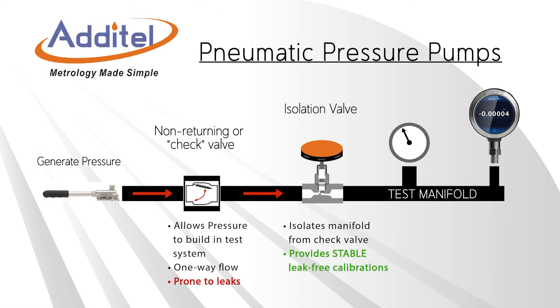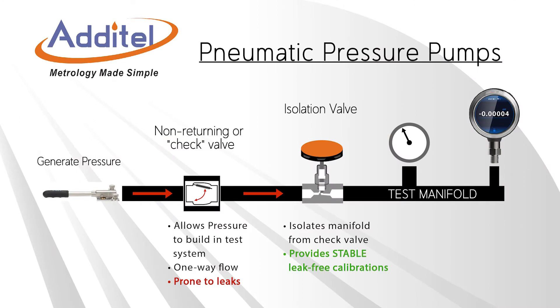A major design advantage of all Additel pneumatic pumps is an isolation valve that allows leak-free stable calibrations. Most pneumatic pumps in the market have non-returning or check valves that allow for pressure to be built up in the test volume. These types of valves are a source of leakage over time. Additel pumps include a valve that isolates the calibration volume from the check valve, providing stable calibrations for years to come.